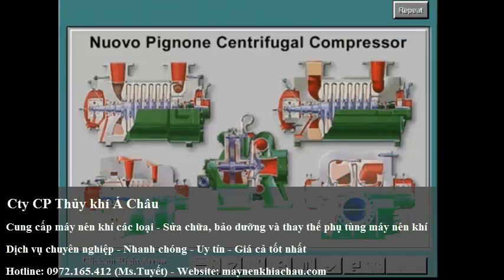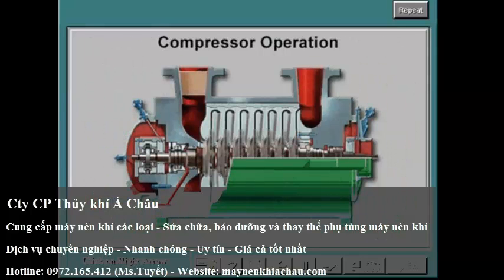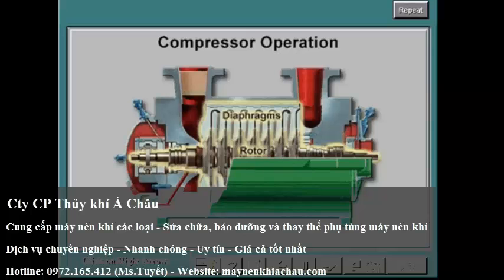In order to more easily recognize the various types of Nuovo Pignone centrifugal compressors, it is important to understand the basic function of a centrifugal compressor. In a centrifugal compressor, a continuous flow of fluid increases its pressure by means of energy given by impellers arranged on a rotating shaft. This type of machine is composed of an outer casing, which contains the diaphragms and a rotor.